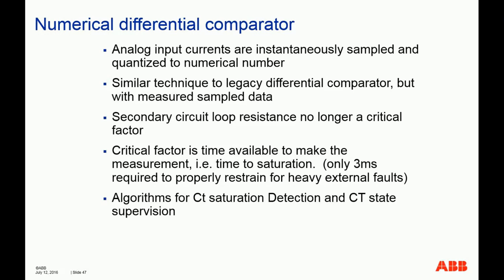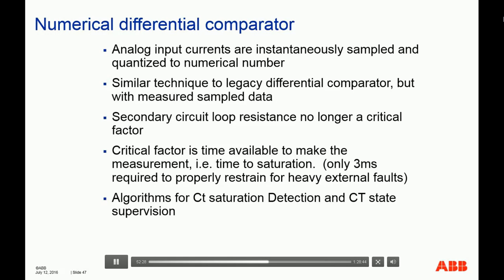Analog input currents are instantaneously sampled and quantized to numerical values. As we know, this is the same for all typical relays. From these digital values, you estimate the phasor associated with the instantaneous current values. Then the fundamental 60 Hz phasor values are fed to the differential functions to calculate the differential current and the restraint current, and compare them against the set slope to determine whether to operate or not. So it's a similar technique to the legacy differential comparator, but with measured sample data.